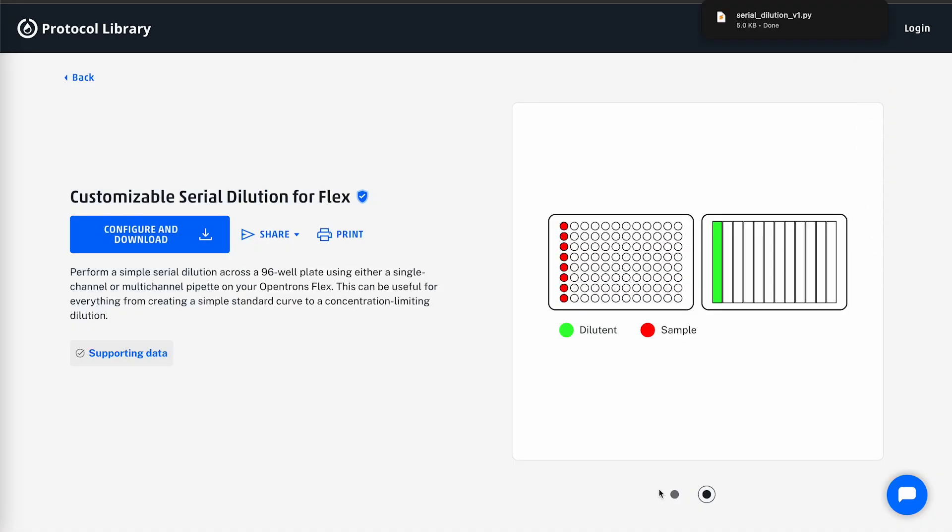The protocol will be saved to my computer. At this point, I can use the Opentrons app to upload the protocol and then run the protocol on my Flex. That concludes this video on how to download a protocol from our library. I encourage you to explore the newly redesigned Opentrons protocol library today to unlock the new possibilities for your lab. Thanks for watching the video.